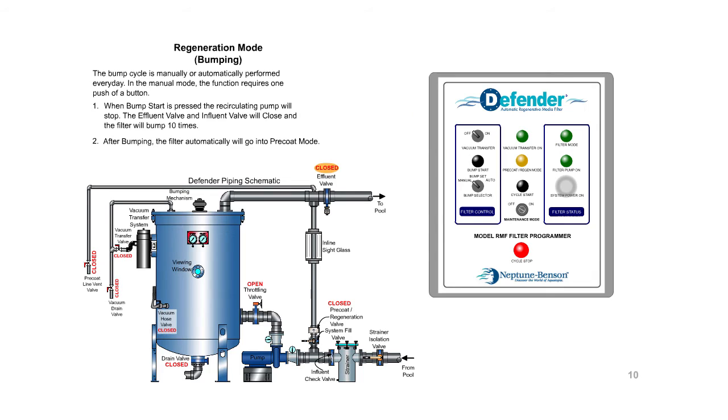The bump cycle is manually or automatically performed every day. In the manual mode, the function requires one push of a button. When bump start is pressed, the recirculating pump will stop. The effluent valve and influent valve will close and the filter will bump 10 times.